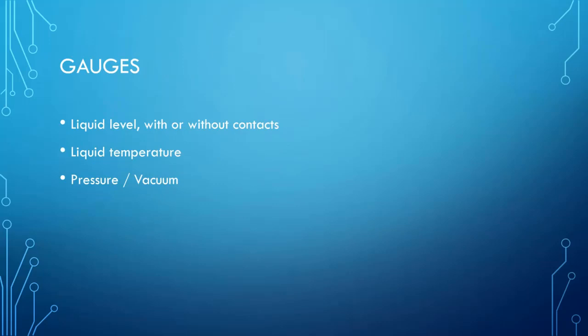Some of the accessories that go on these transformers, both pad mounted and substation type. This is pretty much the bare minimum. This is a liquid level gauge. It is part of the ANSI standard gauge package, so chances are you're going to get one no matter who you order the transformer from or who you specify it in. And a liquid temperature gauge is also standard. And many times a pressure vacuum gauge is, depending on the size of the transformer.